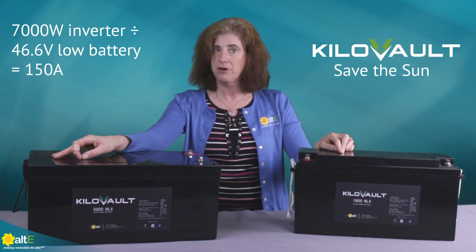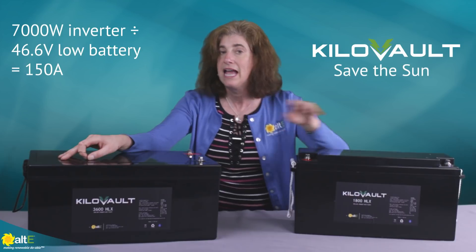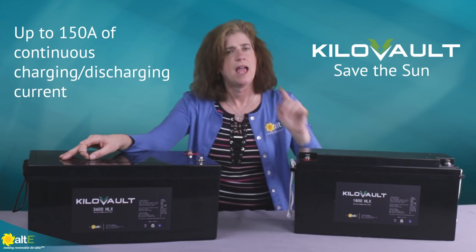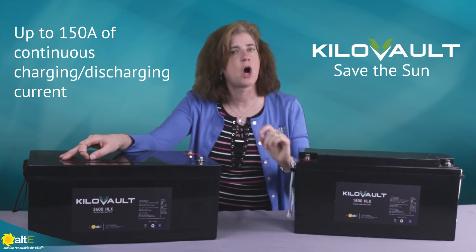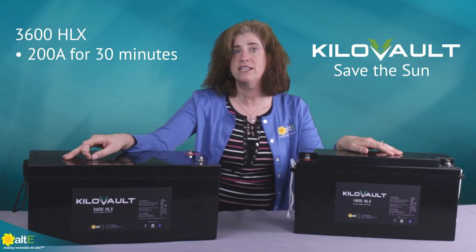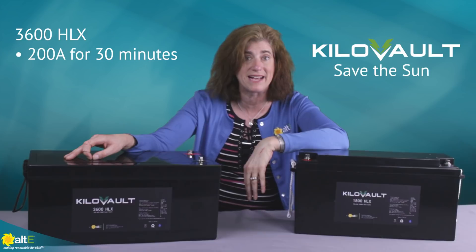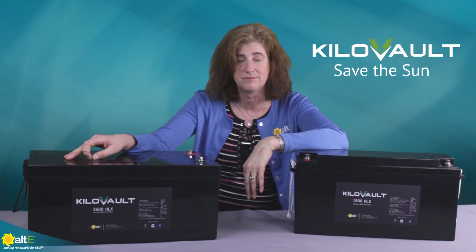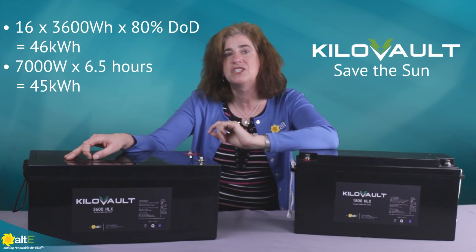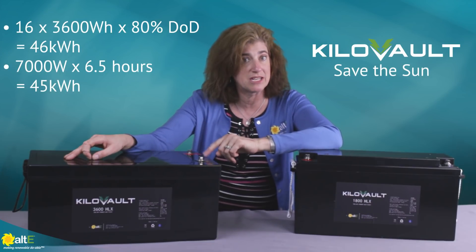A 7,000W inverter can draw as much as 150A from a 48V battery bank. A single string of the KiloVault 1800 batteries can supply that current — not just briefly, but as a constant draw of 150A. If you have a string of 4 HLX3600 batteries, they can sustain up to 200A for 30 minutes before needing to drop back to 150A. Run at 150A, the HLX3600 batteries would go 6.5 hours full tilt at 7kW until the battery reaches 80% depth of discharge.